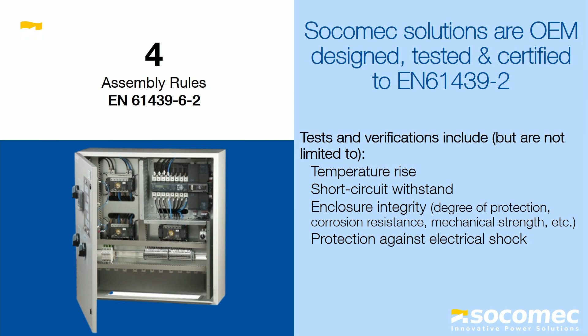So it's really important to test everything together as it is, and not just in isolation. Once you've tested that product, the installer should be asking for proof that it's been tested as an assembly, the certificate of test, and that should form part of the handover documentation, to say: I've installed this equipment to the relevant standard, and it's been tested appropriately. There's documentation.